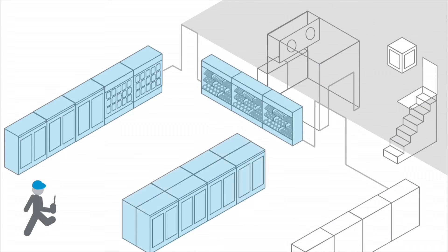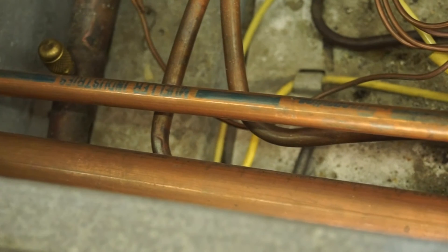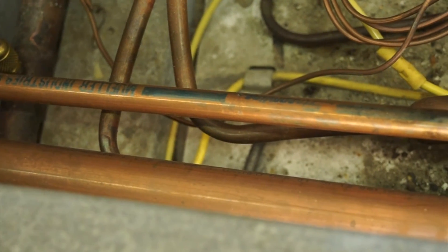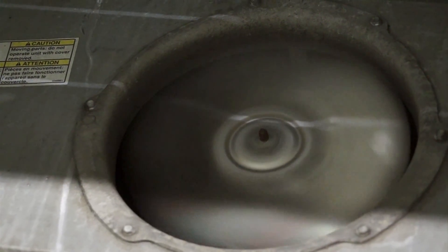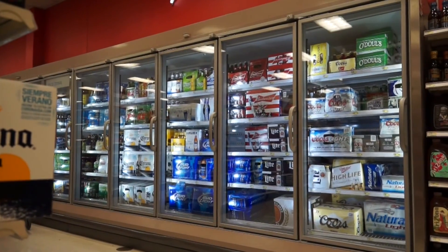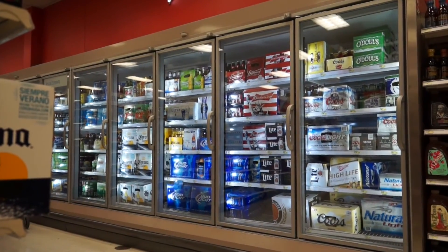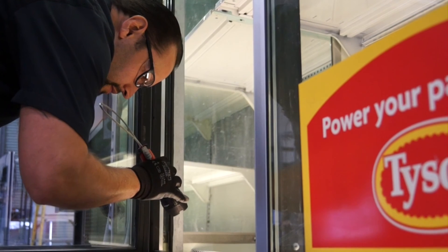Find all display cases and identify any overhead or underground pipe locations. Check for obvious problems and look for oil traces or stains. Make sure all the refrigeration case fans are running, and check cases for excessive airflow. If there is a leak, air movement can change the refrigerant's path.